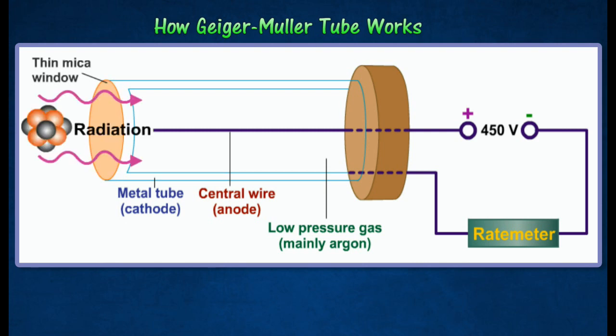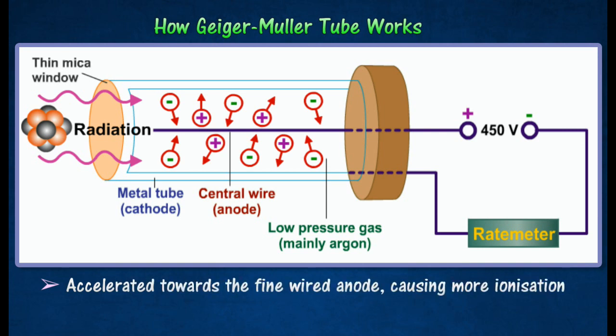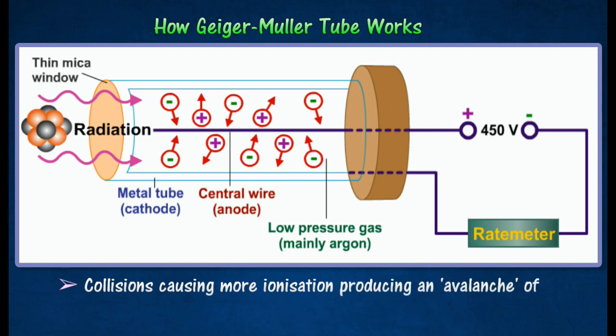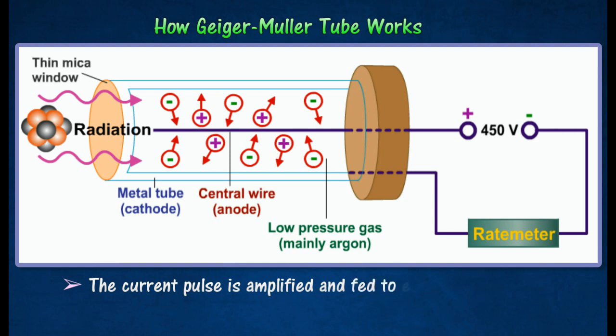When radiation enters the tube, it produces argon ions and electrons. These are accelerated towards the respective electrodes. These accelerated electrons collide with other argon atoms, causing further ionization and producing an avalanche of electrons. On reaching the electrodes, the ions produce a current pulse which is amplified and fed either to a scaler or a rate meter.